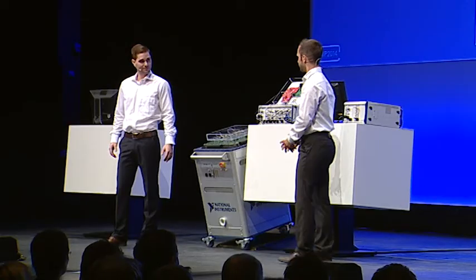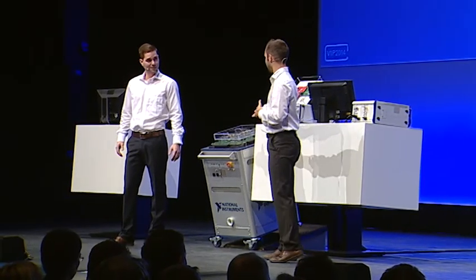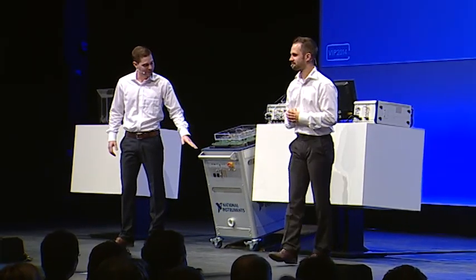Okay, so Travis, can you tell us how this beauty came to be? Well, we definitely did not develop it in a vacuum. We worked with many lead users who not only gave us feedback, but they even deployed our early engineering prototype units onto their production floor. And with some optimizations, we were able to get up to 500,000 parts per day of test throughput on a single site. We also worked with industry experts like Reed Ashman and Sisu Devices on the elements of the system that we wanted to get correct the first time.